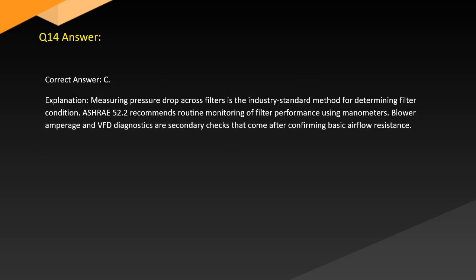Answer. Correct answer: C. Explanation. Measuring pressure drop across filters is the industry standard method for determining filter condition. ASHRAE 52.2 recommends routine monitoring of filter performance using manometers. Blower amperage and VFD diagnostics are secondary checks that come after confirming basic airflow resistance.